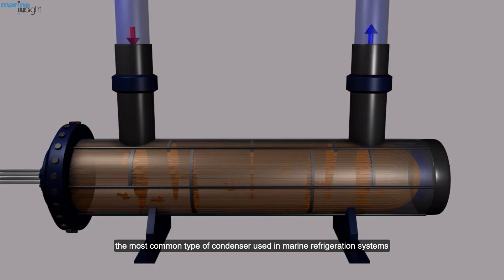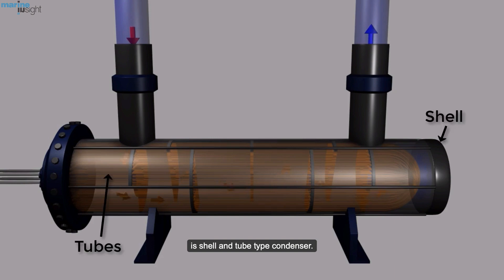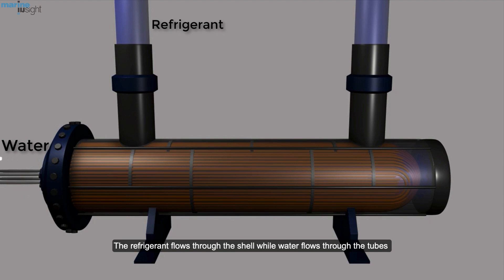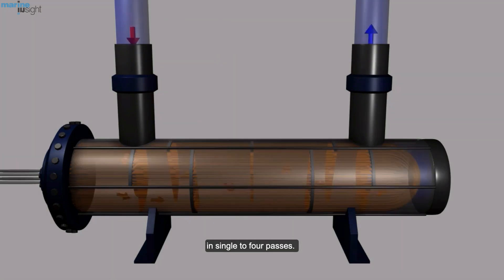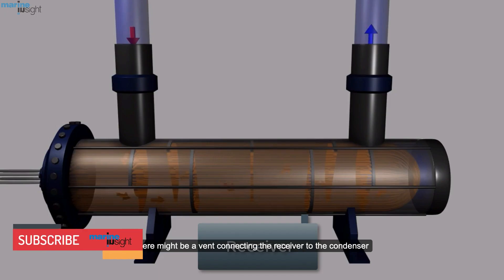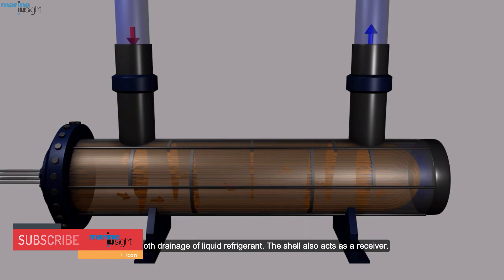The most common type of condenser used in marine refrigeration systems is shell and tube type condenser. The refrigerant flows through the shell while water flows through the tubes in single to four passes. A separate tank which will act as a receiver can be integrated with the condenser. There might be a vent connecting the receiver to the condenser for smooth drainage of liquid refrigerant. The shell also acts as a receiver.